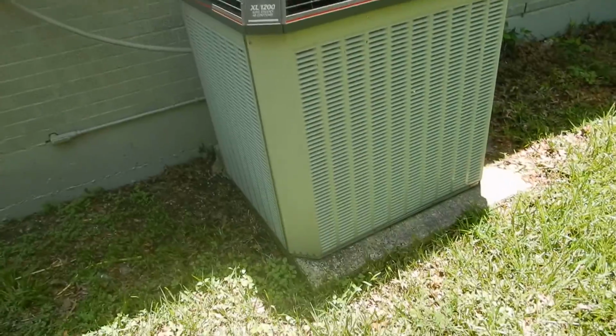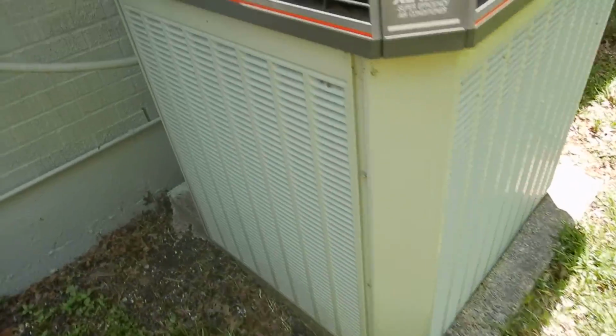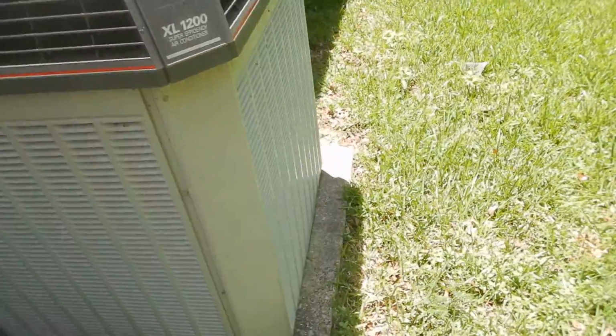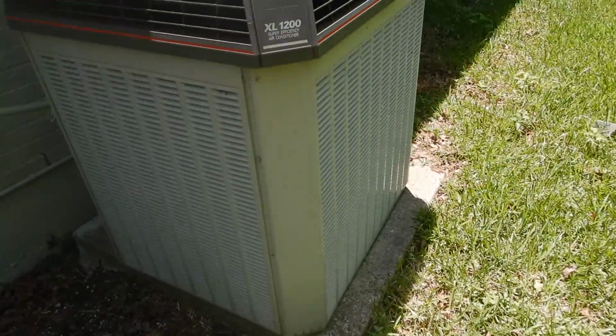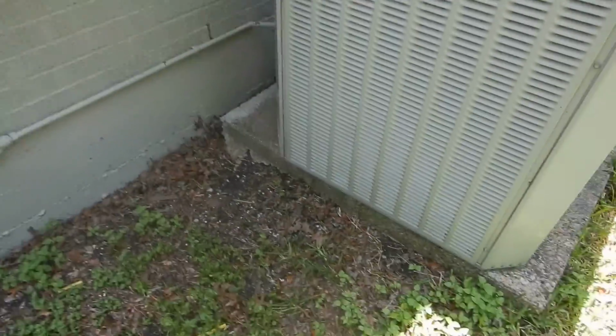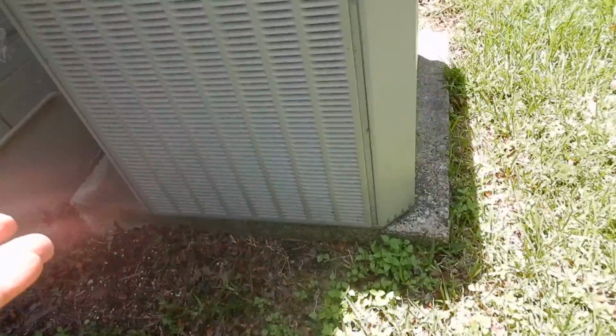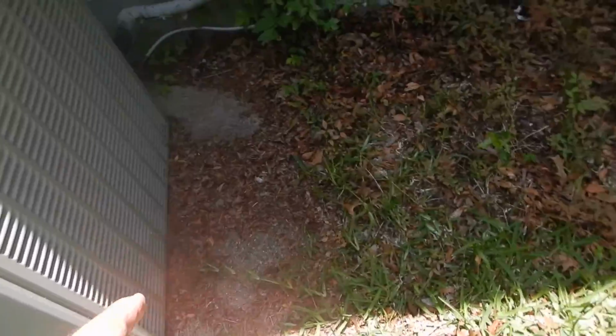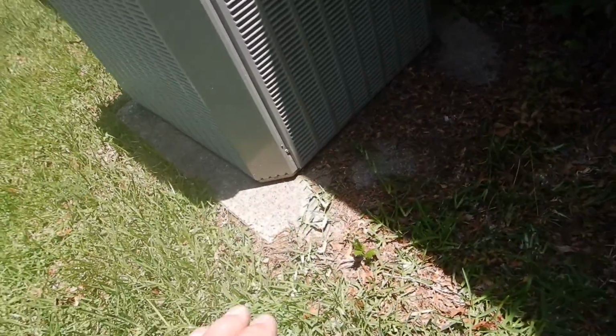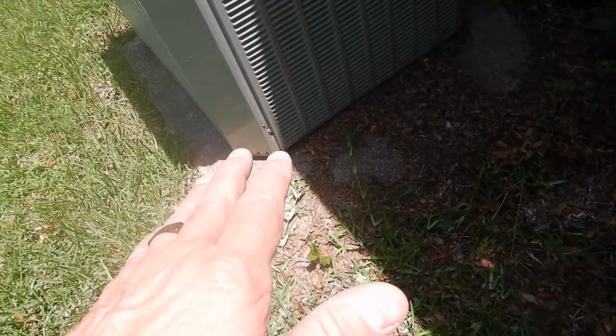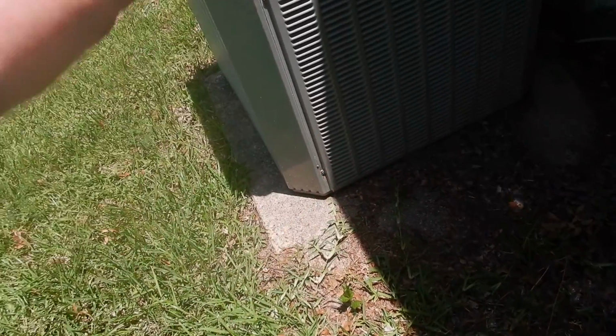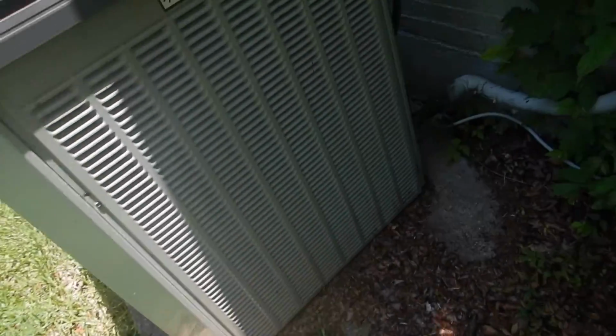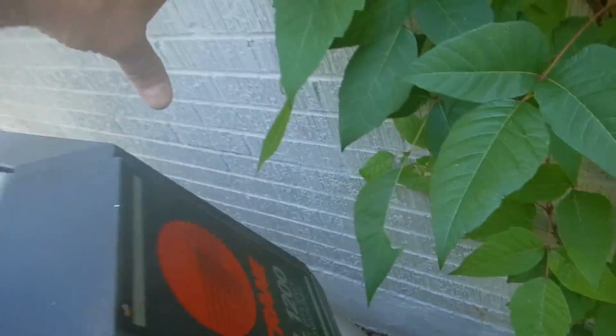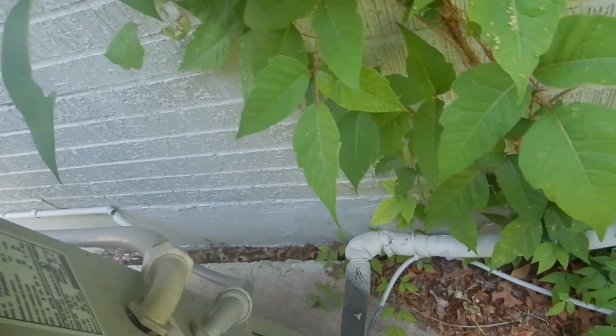This is the HVAC condensing unit here at the back of the house. It's not sitting on the pad exactly right. You've got all this pad over here, but this pad is sunken. It's closer to the ground than 3 inches. It should be raised up off of the ground at least 3 inches. There should be 12 inches of clearance behind it for the air to circulate through there.